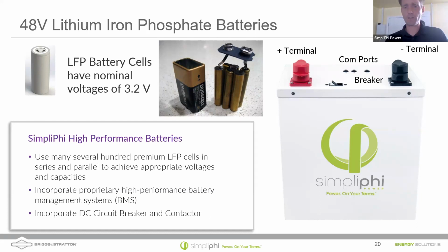Well, if you have that many cells in series, you're going to have to pay attention to the weakest link in the chain. You need to make sure that all the cells maintain a balanced charge and that those cells are monitored during a charging and discharging event. And so what does that? Inside the battery, in addition to all these cells, all lithium batteries have a battery management system. And inside this battery at the very top is a very sophisticated, high-end BMS unit that we use to allow for communication, balancing of charge, temperature monitoring, and many other things. So we're going to get into that. That's the point of today's talk.